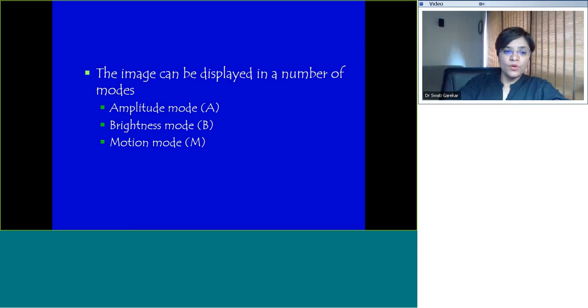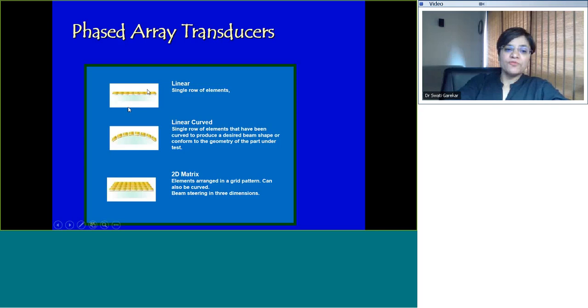The image that comes back can be displayed in a number of modes: the amplitude mode, A mode, brightness mode and the motion mode. The arrangement of the probe varies. You can have a linear probe that our radiologist colleagues use, a linear curved probe, a single row of elements that are curved to produce a desired beam shape, which we use for our fetal echo. Then there's a 2D matrix or 3D matrix probe where the elements are arranged in a grid pattern.